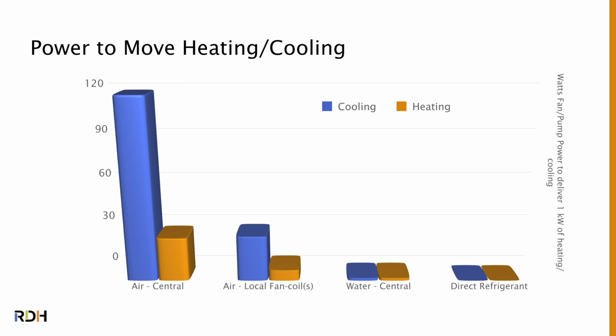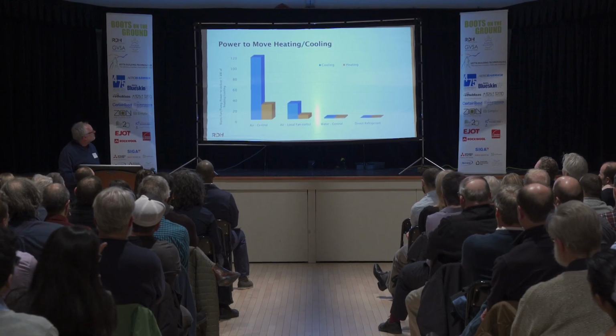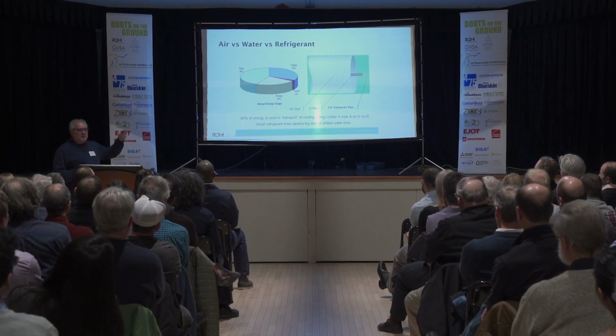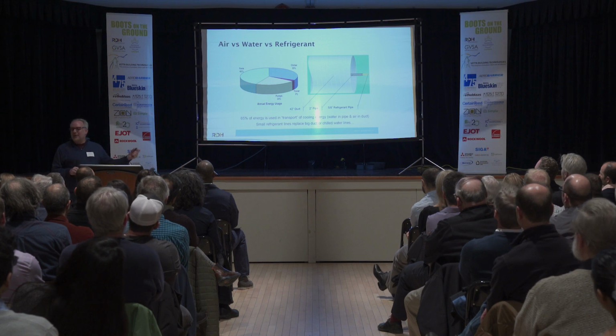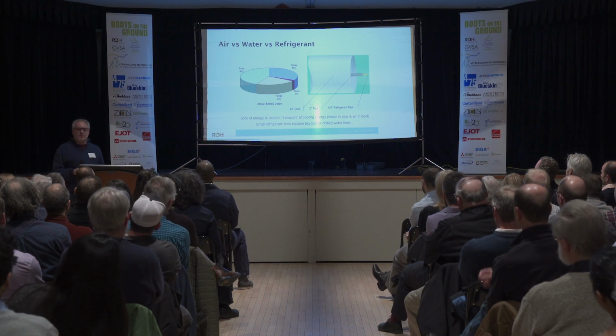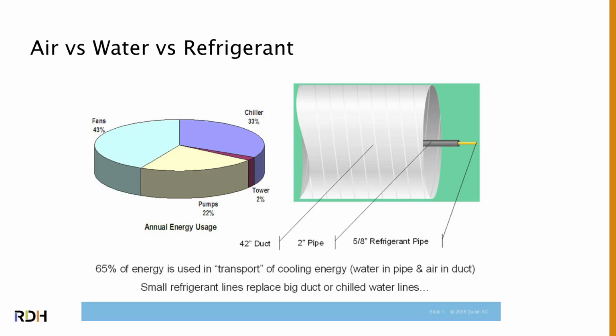So that's kind of why we like to heat and cool with water instead of air, and then we have local fan coils here. And also that translates into the size of your pipe. How big is the pipe you need or the duct you need to move this heating and cooling around the building? The duct, the pipe, and the refrigerant is the tiny little point down there. Now the refrigerant line still needs insulation around it, so it ends up being about the same size as the pipe in the end.